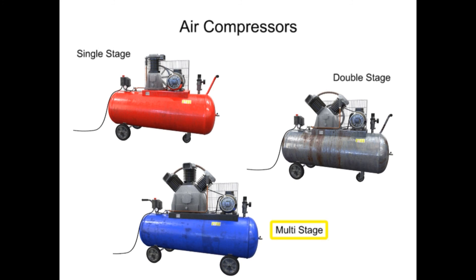On these larger compressors, cooling may take place by circulating water instead of air. To reach a pressure of 2,500 PSI, as many as 6 or 7 stages may be needed with cooling between each stage. Their versatility makes compressors one of the primary components in air production.